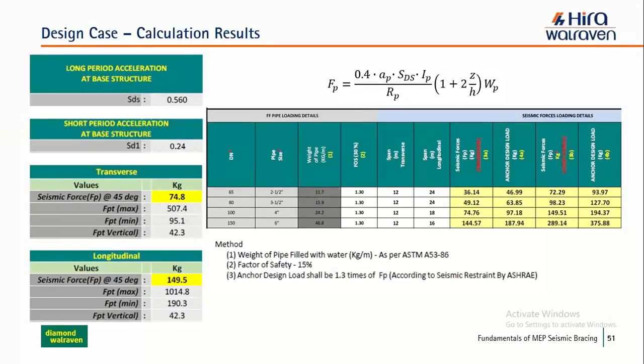By using this equation, based on soil parameters, we have computed SDS and SD1, and then based on this formula we have computed the seismic force at certain angles, because wires shall be applied at some angles. We cannot consider the vertical force for wire application or any application for bracing. Angles need to be considered. Then again the same formulas for maximum and minimum, we need to follow the minimum, and then the vertical should be designed.